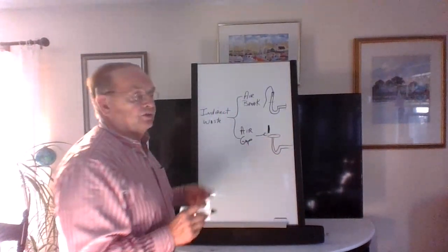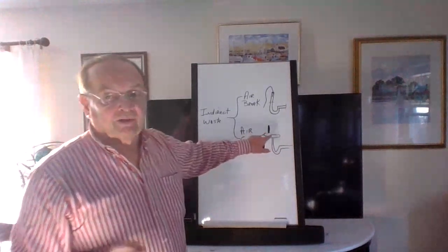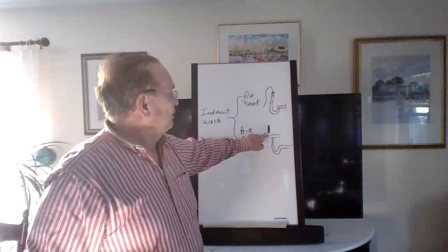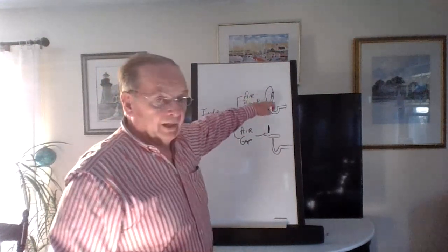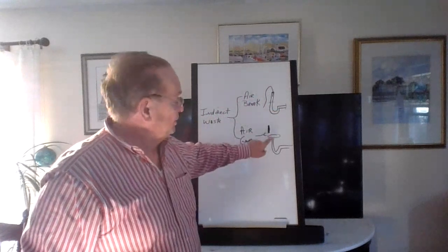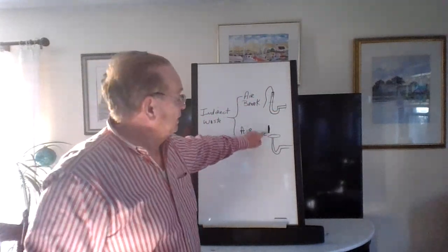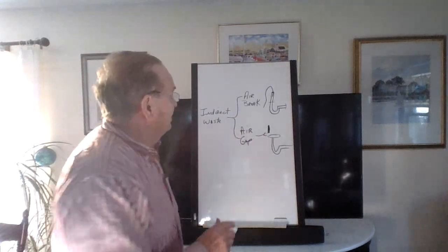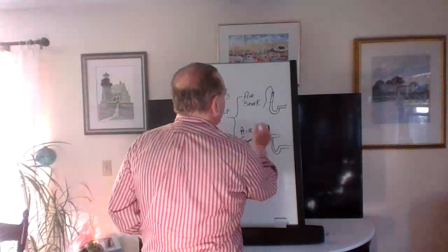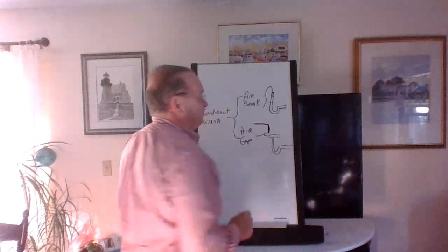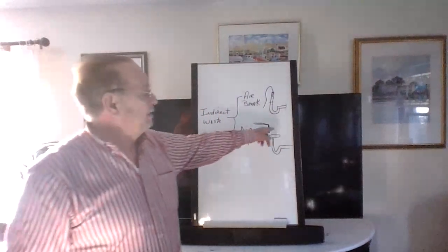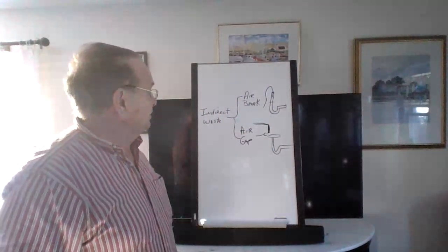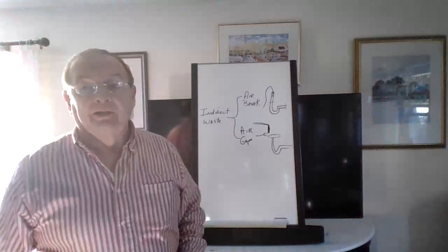We'll say it's 3 inches. Okay, that's that through the free atmosphere that they're talking about. Okay, so this one here hooks right in. This one does not. So this one is actually a safer bet because it can't siphon anything out of there. Okay, so this would be an air gap. This would be a pipe coming down from somewhere else, right? A drip. It could have a couple of these. So there's an example of an air gap on the drainage side.